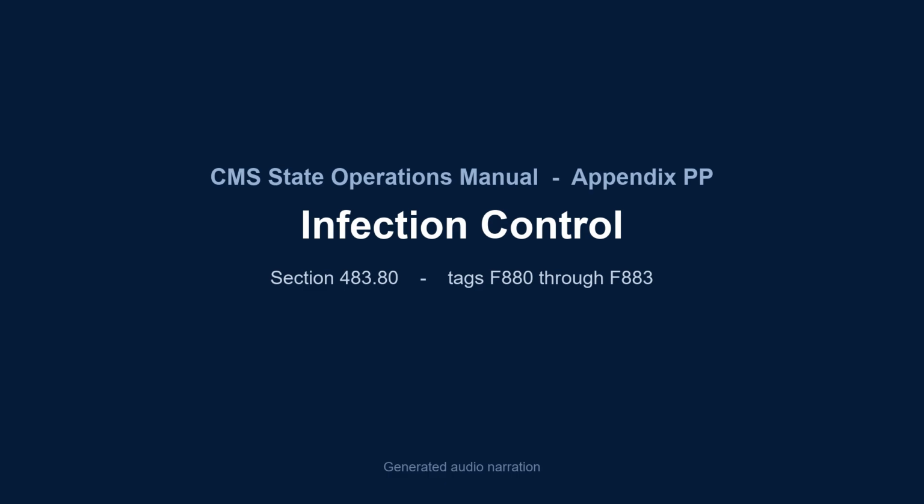Non-critical items require cleaning, followed by either low or intermediate level disinfection. Following manufacturer's instructions, disinfection should be performed with an EPA-registered disinfectant labeled for use in healthcare settings. All applicable label instructions on EPA-registered disinfectant products must be followed, e.g., use dilution, shelf life, storage, material compatibility, safe use and disposal.